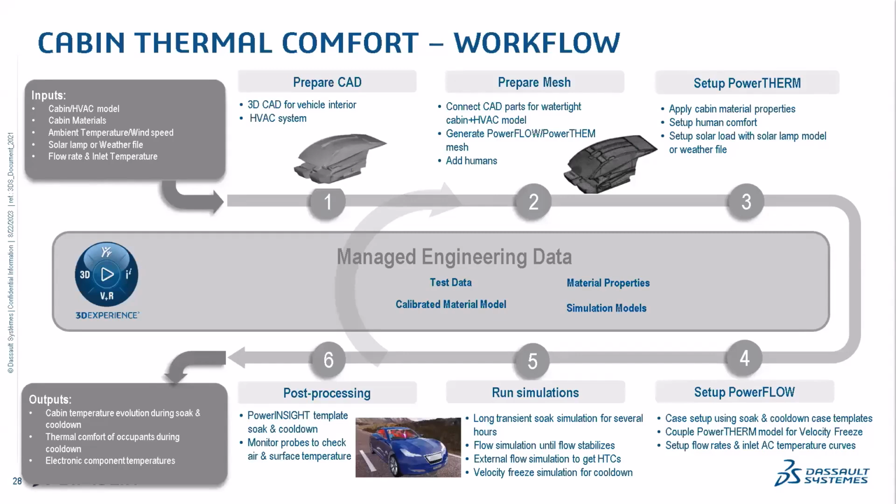In most of these simulations, we're looking at the geometry for the cabin interior as well as the HVAC systems. And because we want to calculate human comfort, we do include the humans in these simulations. However many humans are supposed to be within the cabin during operation, we want to make sure we have those available and properly postured in our model.